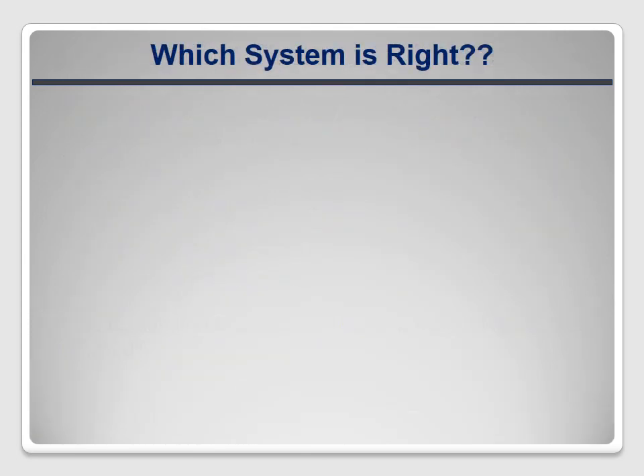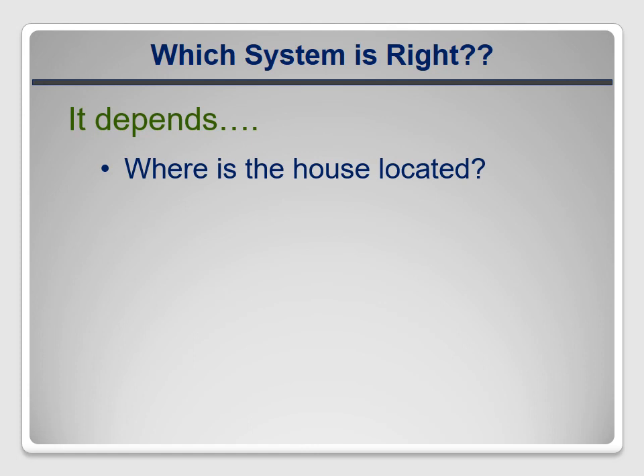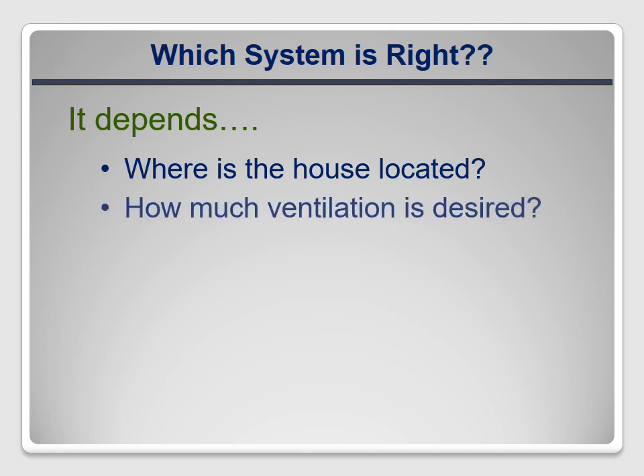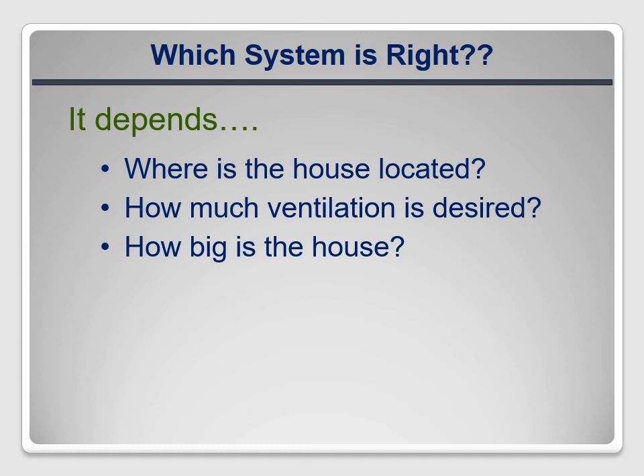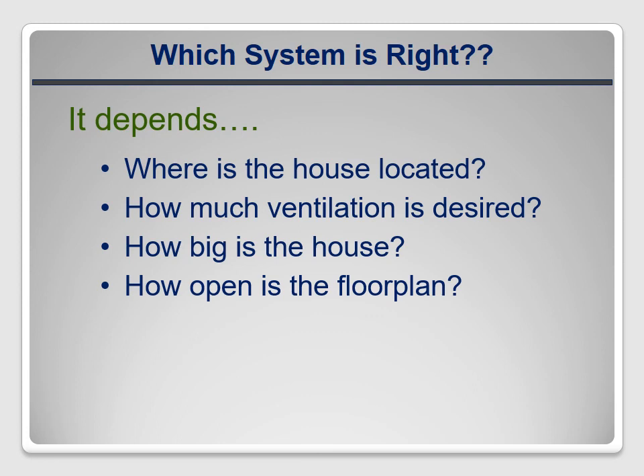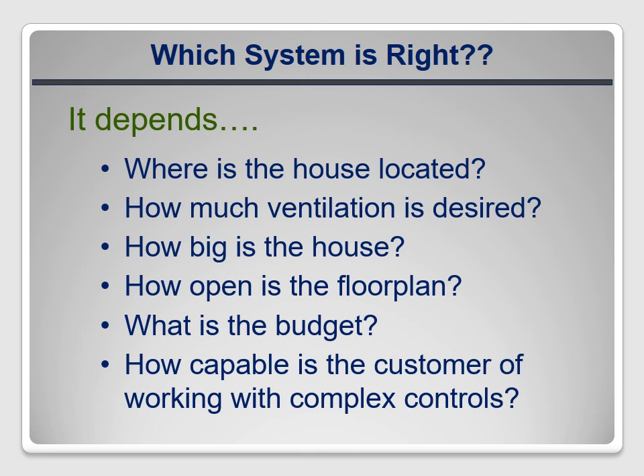So how do you decide which system is right for your customers? Well, it depends. The location of the house is important — because of potential moisture issues, exhaust-only systems are better than supply-only systems in cold climates, but the opposite is true in warm, humid climates. Another consideration is the amount of ventilation needed. If it's really high, an HRV may make sense to reduce the energy penalty. If the house is big, a system with multiple supplies or intakes probably makes sense to ensure that the whole thing gets fresh air. But if it's small and the floor plan is very open, then a single supply or intake will probably be adequate. Of course, you have to consider the available budget. And finally, think about the controls and whether the specific customer will be willing and able to understand and use them. If you design the system well, it will provide the customer with healthy air for a long time.